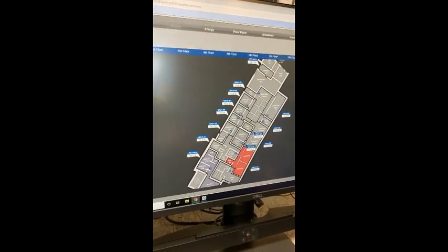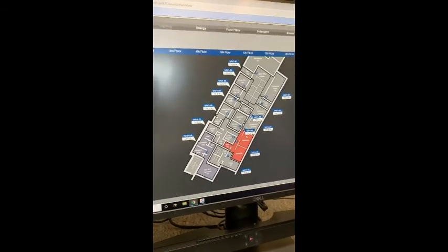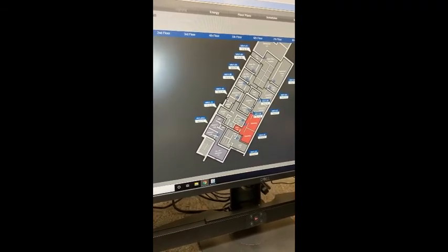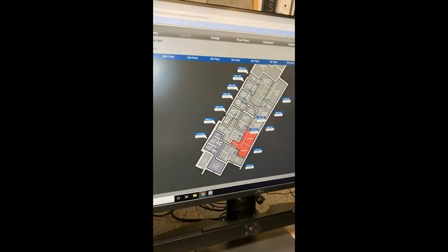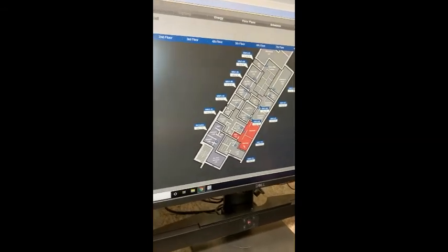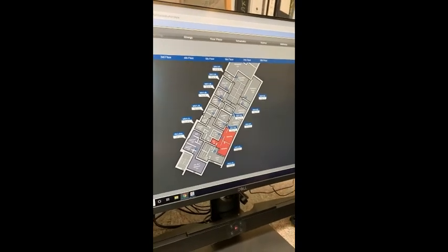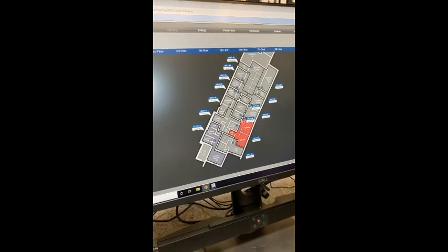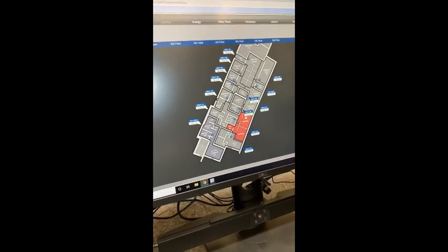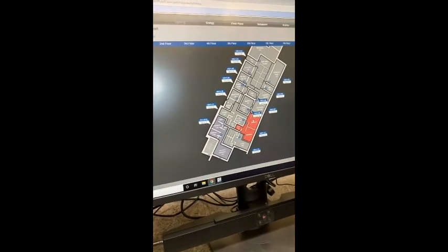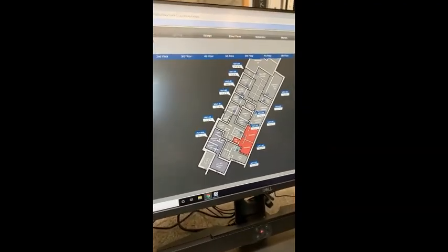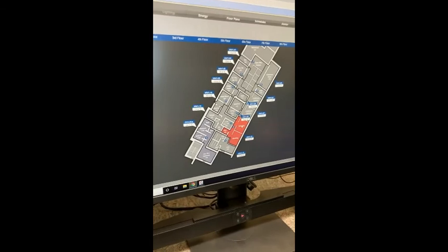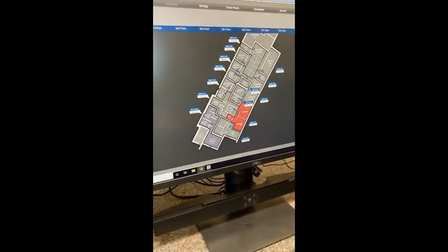Same thing here with where we showed you that the temperature value reading background in the summary would go red or blue. So will the floor plan area for the zone. So we can see this zone right here is over temp. And the black lines basically represent the edge of the zones, because a lot of the time there won't always be a wall that represents it. So we draw the black line within the walls to show where the different zones start and stop.